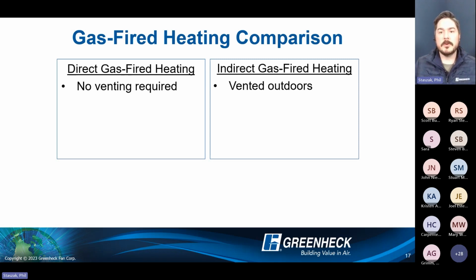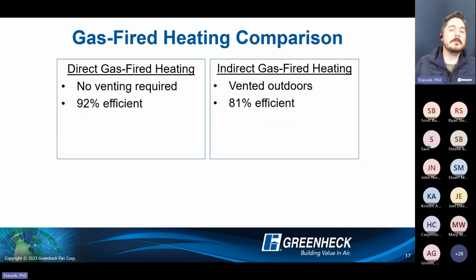Now, with indirect, you do need venting outdoors. Most of these units are installed outdoors, so that's really not a big concern because it's just going to vent right out to the atmosphere. But if it is an indoor installation, that's a consideration for the installer. You're going to need an intake pipe and a discharge pipe coming from that furnace to vent the flue gases out, and at lower efficiency. So we're talking 92% efficient with direct gas fired heating versus 81% efficient with indirect. That's typically what you're going to see in the industrial and commercial market.